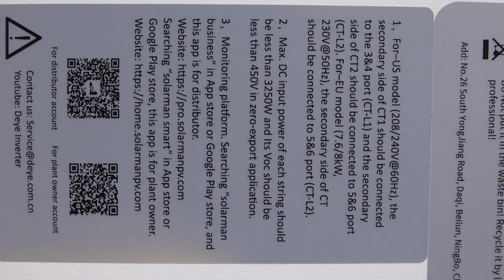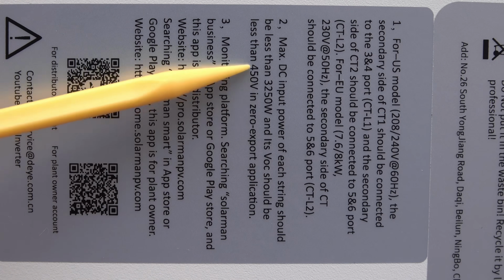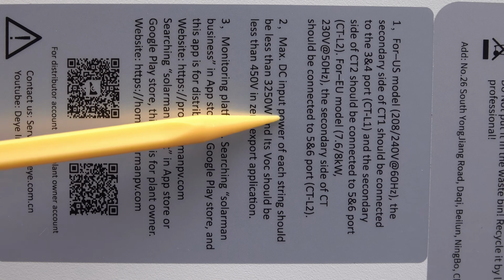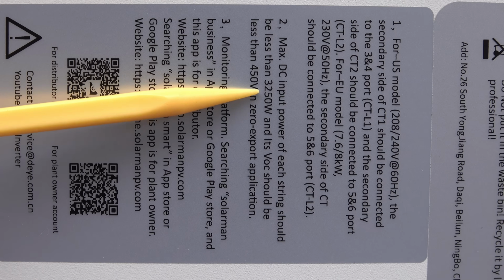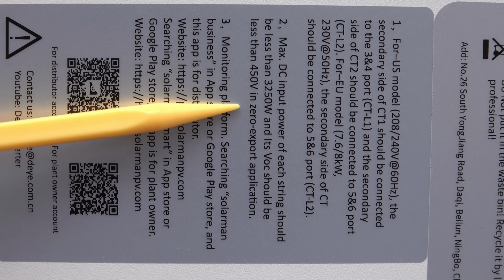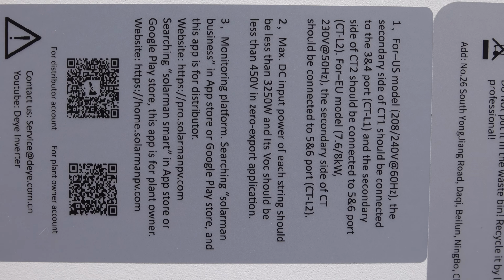Now, unfortunately, I might have goofed the sizing, because it says here the PV input power per string is 3250 watts, and I've actually got 3.33, I think it is. So I might have to remove a panel from each of my strings.